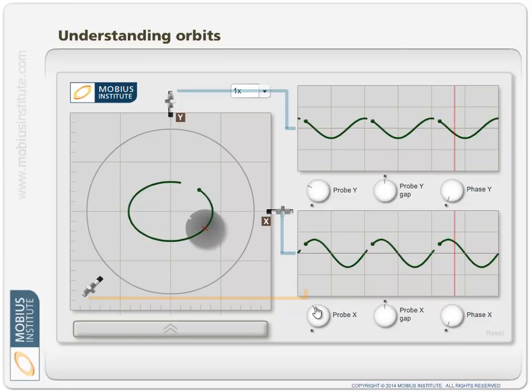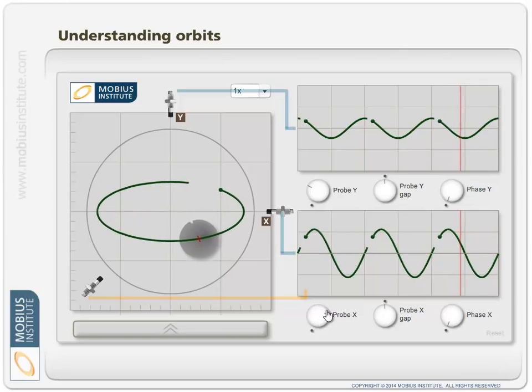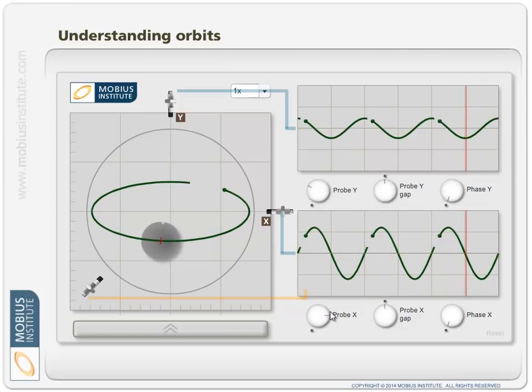And of course we can make it more extreme, and when you saw something like that, you'd be saying, wow, what's happening? Is there a lot less stiffness in this axis, or is there a lot more force acting vertically, which is restricting its movement vertically? So that's the thing, we don't really know exactly why the shape is like this. Is it simply allowed to move more in the X direction, or is it not allowed to move more in the Y direction? But either way, our proximity probes are showing us that.